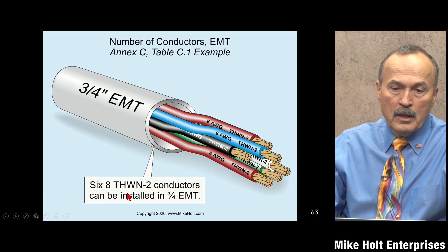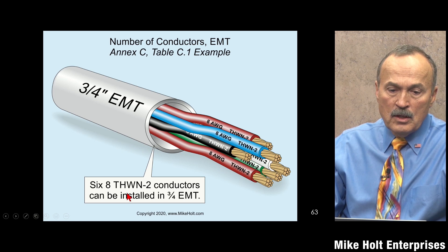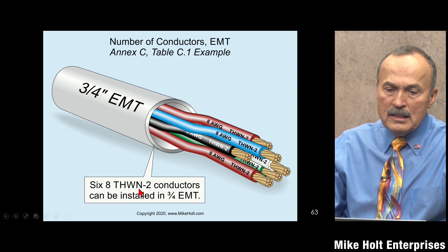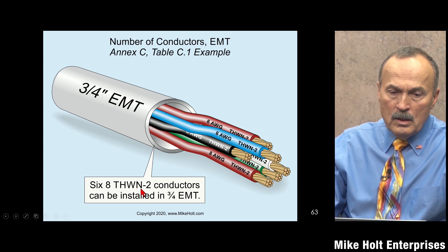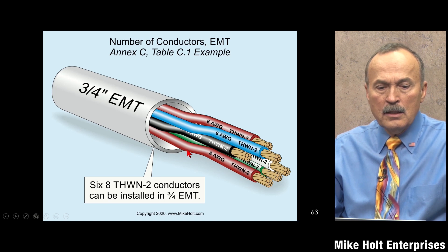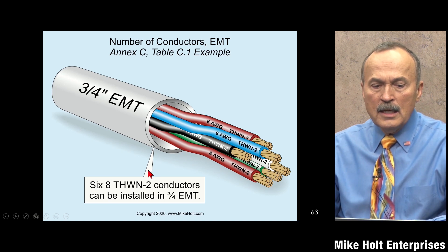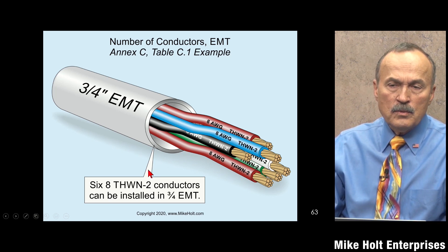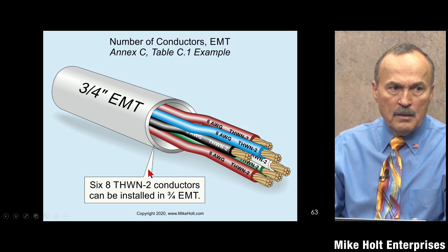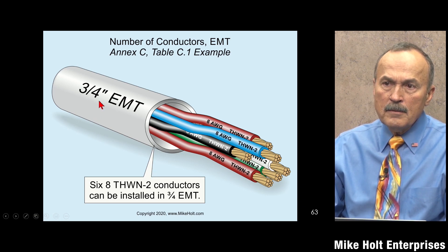Next example: if you had six #8 THWN-2 conductors, what size raceway do you need? You take the insulation type, the number of conductors, and select the raceway - working it backward. That comes out to three-quarter inch.